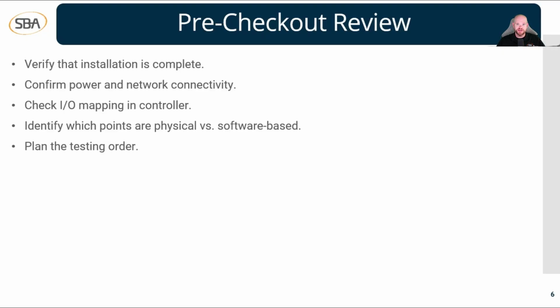This is the pre-checkout review. So we're going through making sure all the installation is complete, and we're confirming that controllers have power, devices have power, and that our controllers and our software, everything is communicating as it's supposed to. So once we've checked that, the next thing we can go on to is checking our input-output mapping in the controller.